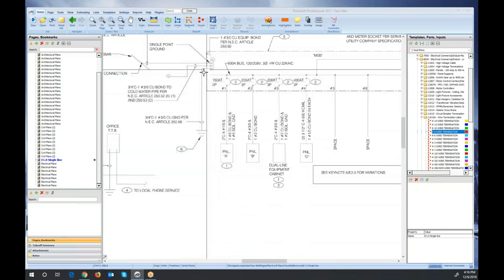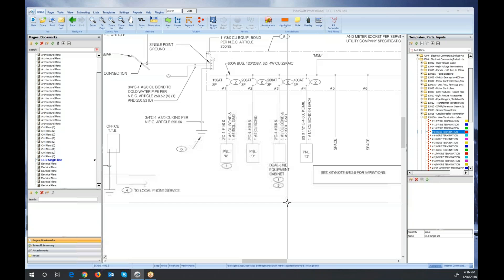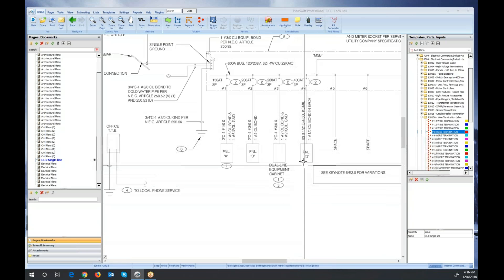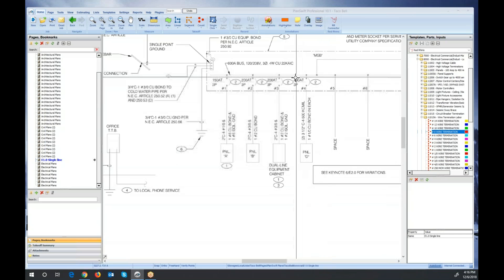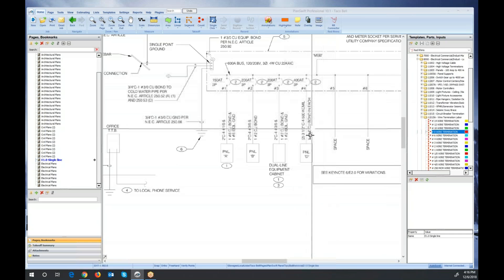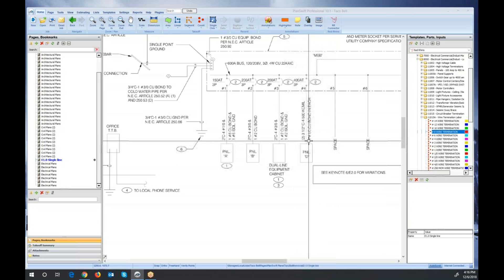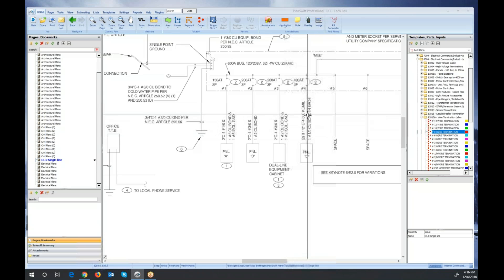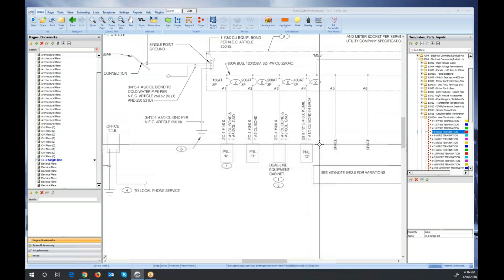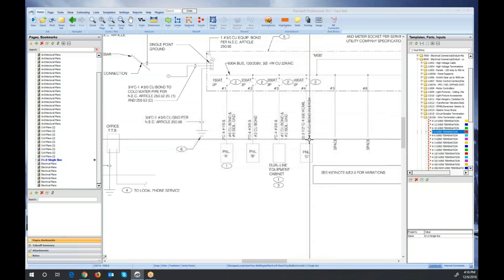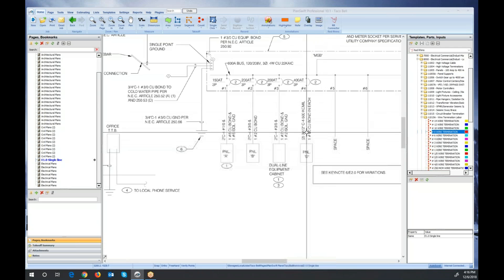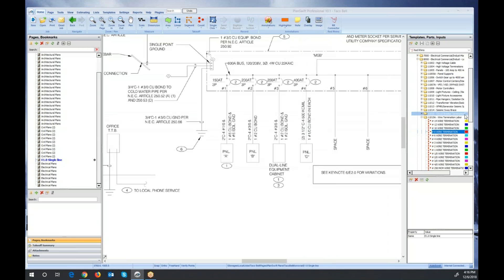Now here's what I want to point out. Also, the ground would require wire termination. But notice this is a 400-amp panel. See the circuit breaker up here, 400-amp? And so it has two 3 1/2-inch parallel 3 1/2-inch with four 500s, and then one 1-aught. So in this case, you'd have to count all eight wire terminations for the eight total 500 MCM wires. Let me just do that right now.